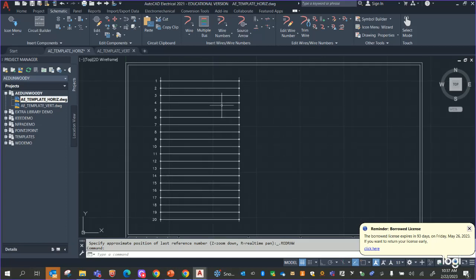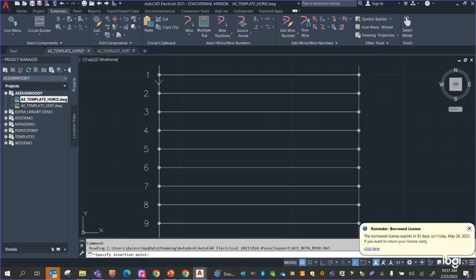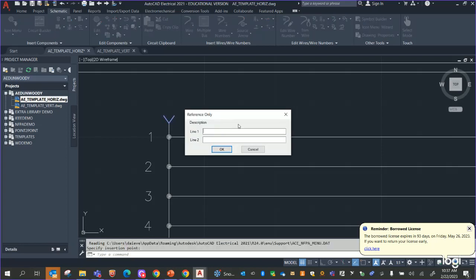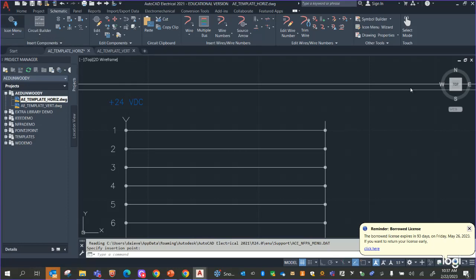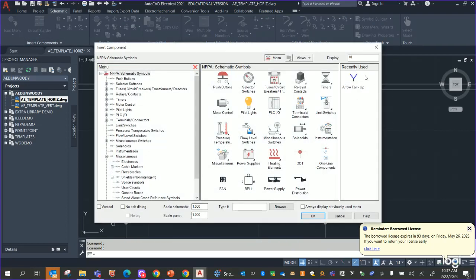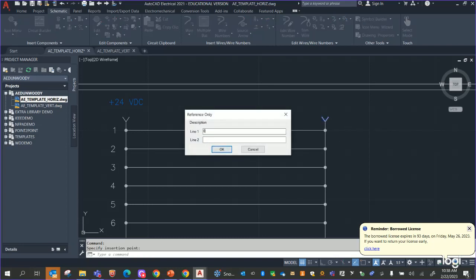One thing I like to do before going much further is insert some reference arrows on the top. I'll go to the icon menu, then to miscellaneous, and then wire arrows for reference only. I like using this little arrow tail-up and placing it on the top of this rail, calling it plus 24 volts DC. So we'll identify that rail as a 24-volt DC rail. Then we'll go over to the other one and do something similar. Once I've used a symbol, it shows up in my recently used, which is handy — I don't have to drill through that submenu again. I'll place that one and label it zero volt common, all caps.